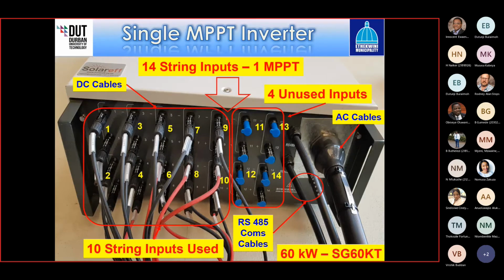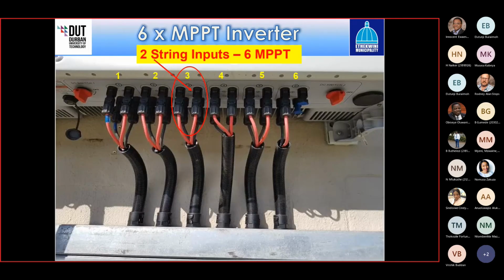So here's an example of an inverter. This is typically a 60 kilowatt inverter. It has 14 string inputs, but it has 1 maximum power point tracker. So in this case, 10 of the string inputs are used and 4 are unused. And here's another example of an inverter. You have 6 maximum power point trackers with 2 inputs per maximum power point tracker.